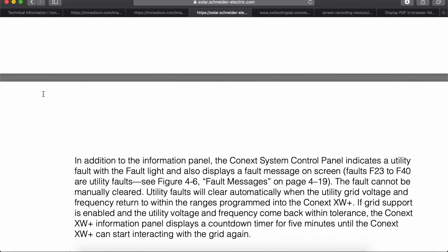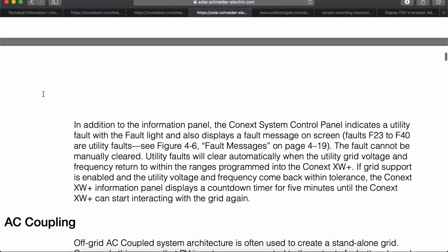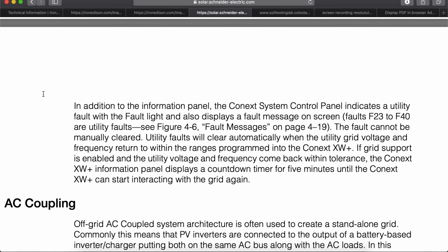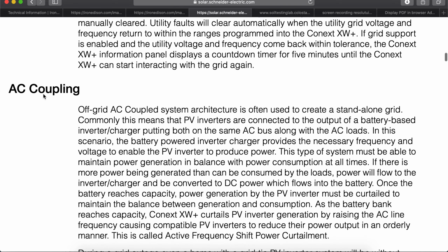In addition to the information panel, the Conext System Control Panel, or SCP, indicates a utility fault with the fault light and also displays a fault message on the screen. Faults F23 to F40 are utility faults. See Figure 4.6 fault messages on page 4-19. The fault cannot be manually cleared. Utility faults will clear automatically when the utility grid voltage and frequency return to within the ranges programmed into the Conext XW Plus inverter. If grid support is enabled and the utility voltage and frequency come back within tolerance, the Conext XW Plus information panel displays a countdown timer for 5 minutes, 300 seconds actually, until the Conext XW Plus can start interacting with the grid again. For linesperson safety, we just don't want to interact with the grid if it's out of range.